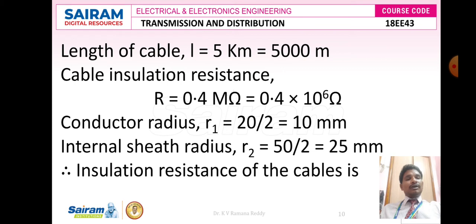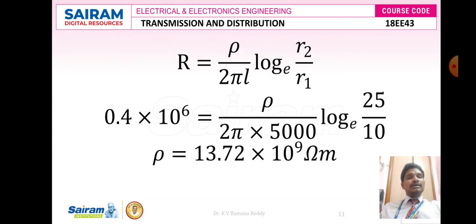From the given data: length l = 5 kilometers = 5000 meters. Insulation resistance R = 0.4 mega ohms = 0.4 × 10^6 ohms. Conductor radius r1 = 20/2 = 10 mm. Internal sheath radius r2 = 50/2 = 25 mm.